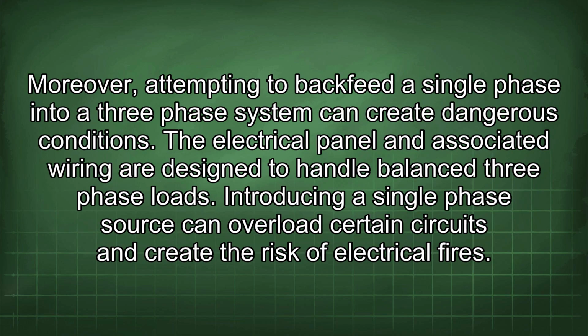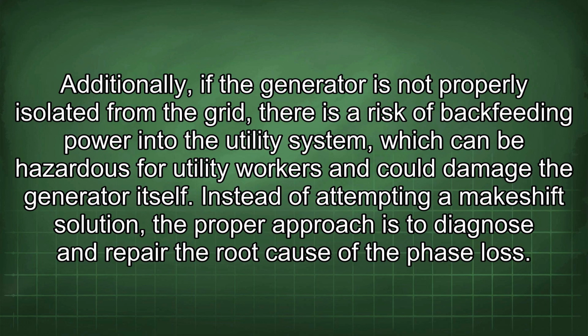Moreover, attempting to backfeed a single phase into a three-phase system can create dangerous conditions. The electrical panel and associated wiring are designed to handle balanced three-phase loads. Introducing a single-phase source can overload certain circuits and create the risk of electrical fires. Additionally, if the generator is not properly isolated from the grid, there is a risk of backfeeding power into the utility system, which can be hazardous for utility workers and could damage the generator itself.